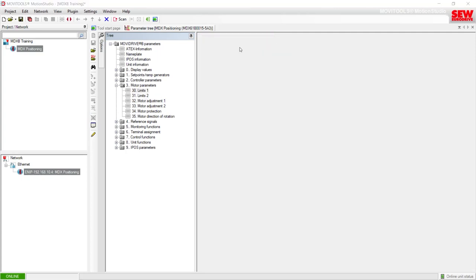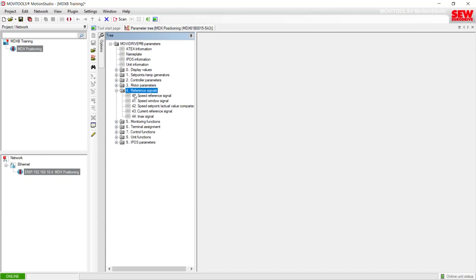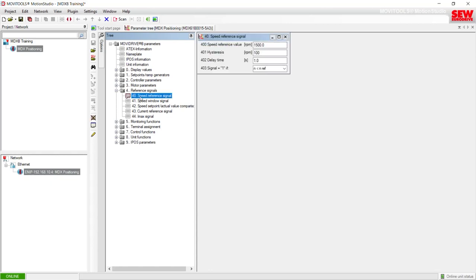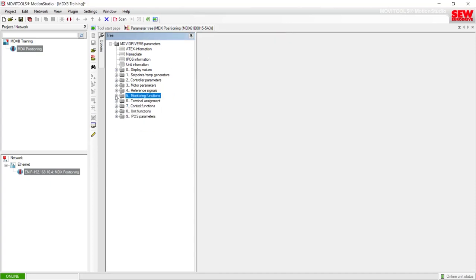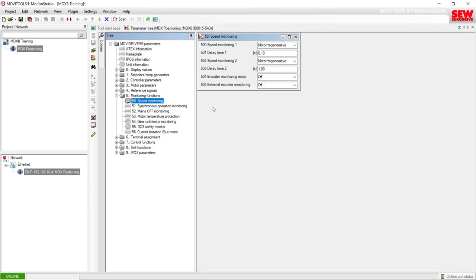Folder 4 is Reference Signals, used if you need to fine-tune how an output of the MOVIDRIVE responds to different speeds or currents — this is where you can fine-tune how your output signal comes on when around a certain value. Folder group 5 is where you can fine-tune how the MOVIDRIVE responds to different functions it's currently monitoring. Item 50 is the most popular one for speed monitoring, where you can adjust how the MOVIDRIVE responds to a speed monitoring fault scenario.